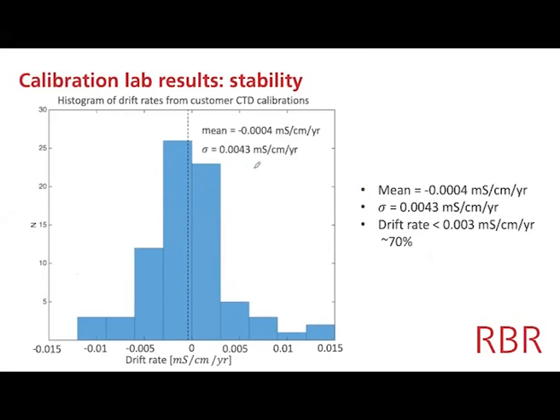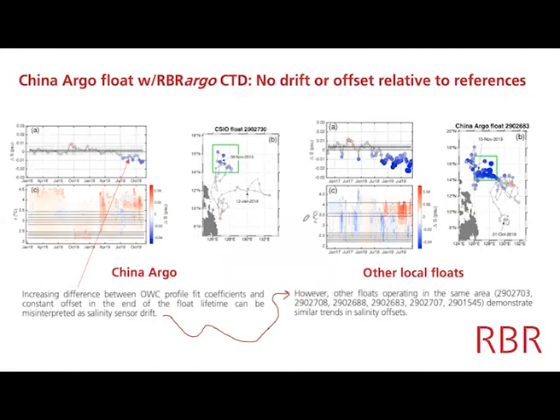So the dispersion of this distribution, the standard deviation, is about 0.004. So that's, 60-something percent of the instruments drift by that amount between calibrations, which is just above, in fact, our calibration accuracy. So recall on our spec sheets, we put 0.01 millisiemens per centimeter per year as a very conservative estimate of the stability. So that's the results from our calibration lab. And the other way we can estimate the stability of the sensor is actually using in situ data on Argo floats. So a number of Argo floats have gone out now with RBR CTDs on them. And we can use that data and compare it against oceanographic references.